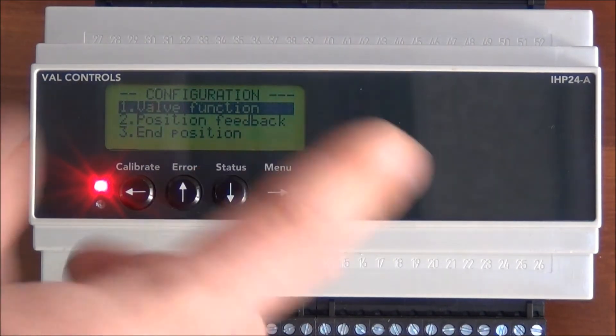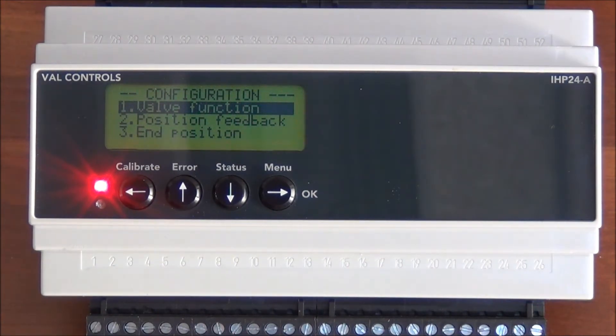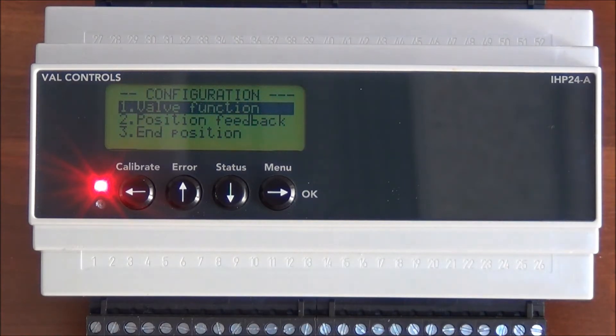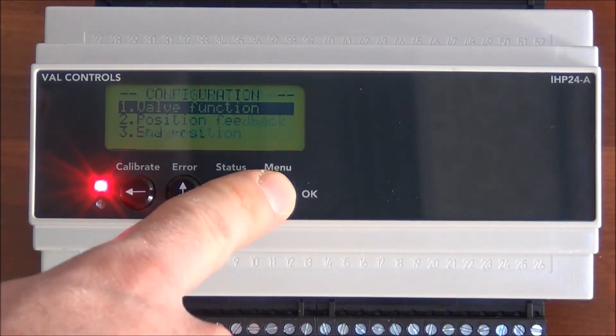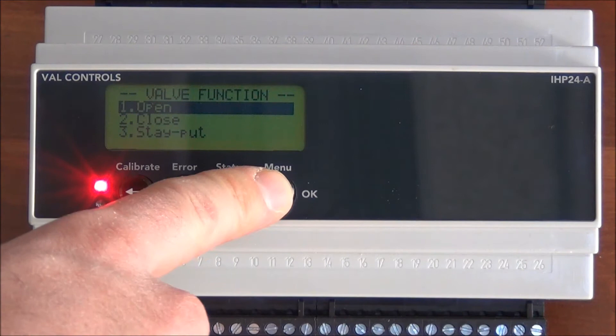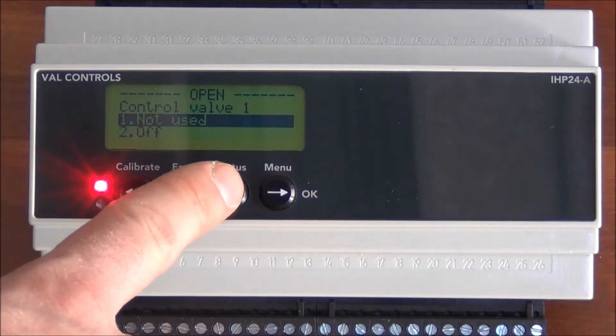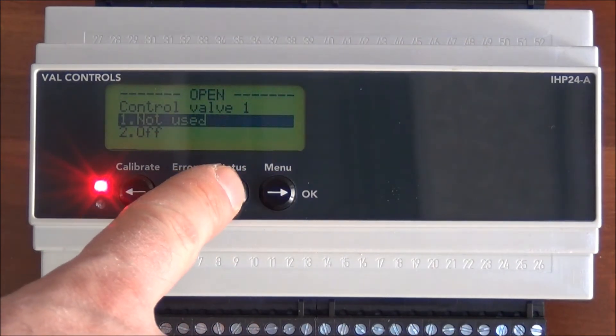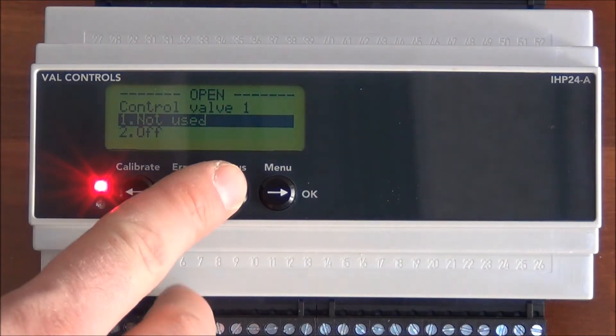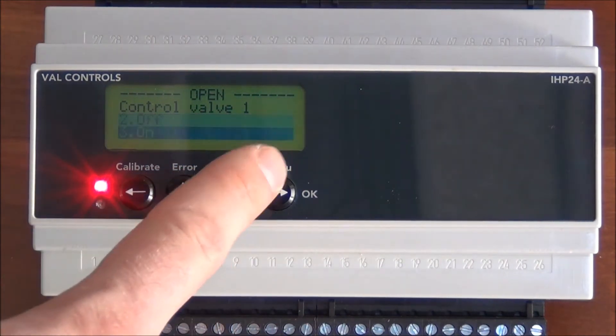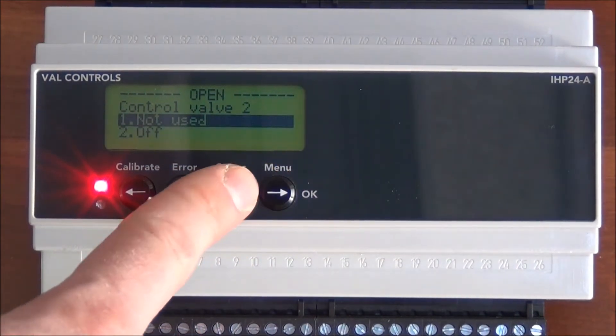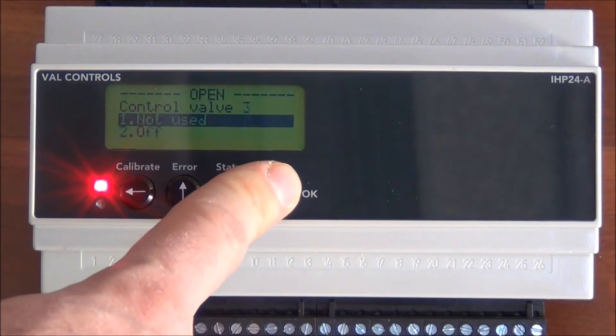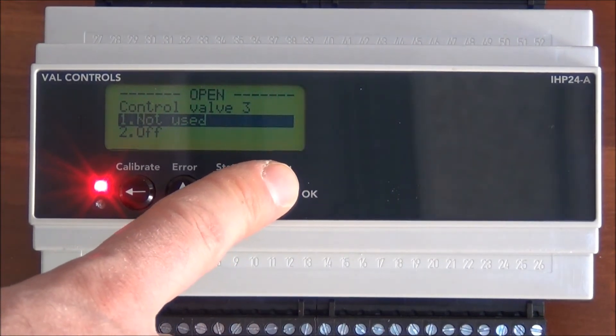In the configuration we have to set how we want the solenoid valves to act when we are opening, closing, and staying put. So I press valve function and choose open. In this configuration, valve number 1, and we have up to 4 valves we can control, valve number 1 is on. Valve 2 is off, and 3 and 4 are not used.